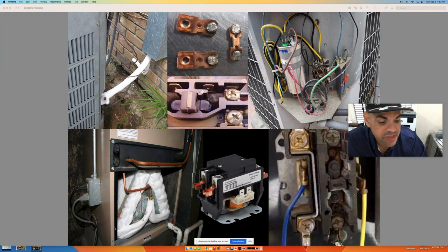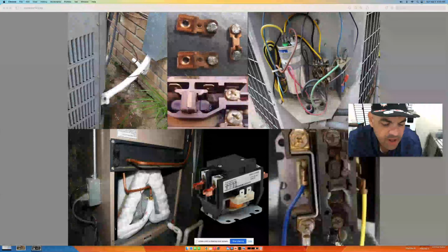Okay, the only thing that you can do to troubleshoot this, if you want to test it out, is there's a little button up on top here where I'm using my mouse. If you notice here in the middle, these contactors go through a lot of wear and tear. Every time this contactor goes up and down, it does arc and it gets carbonated. There's two ways that this contactor can go bad. It's either going to get stuck, and the contacts are going to be so bad that it's not going to send any voltage to the other side of your contactor.